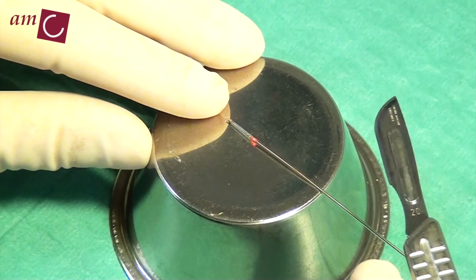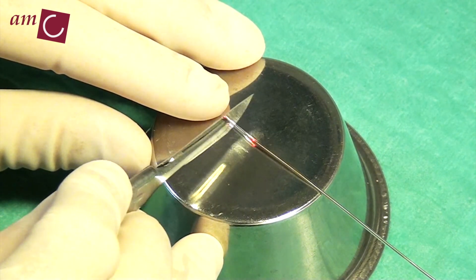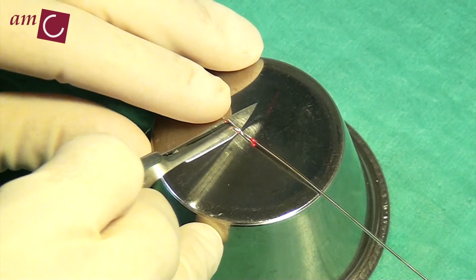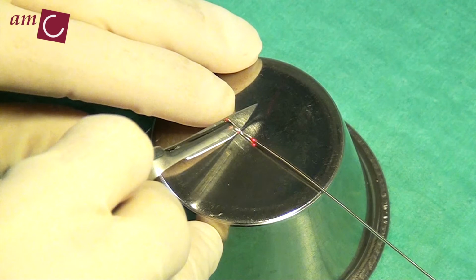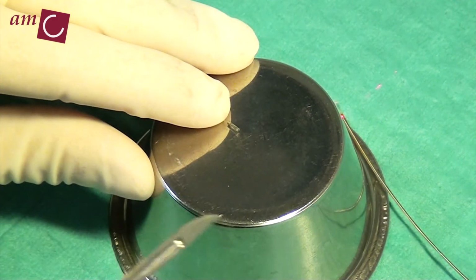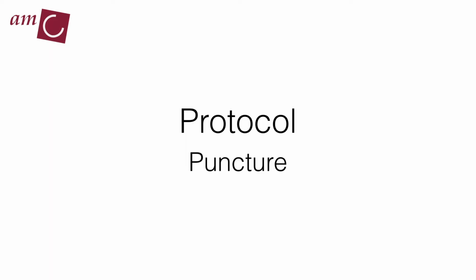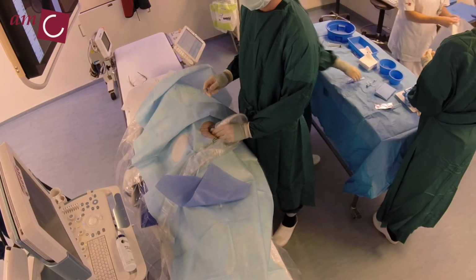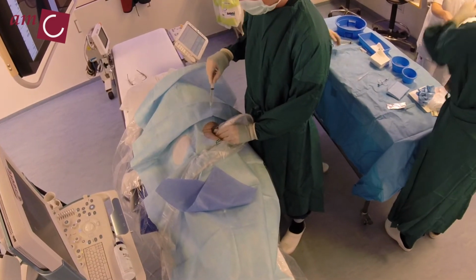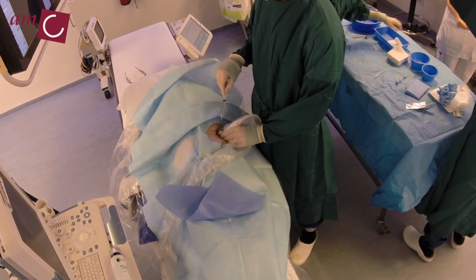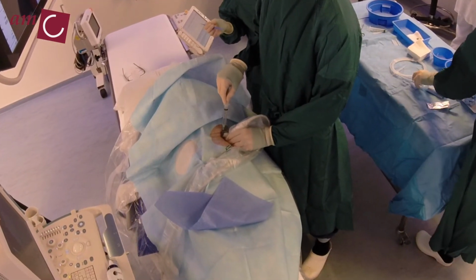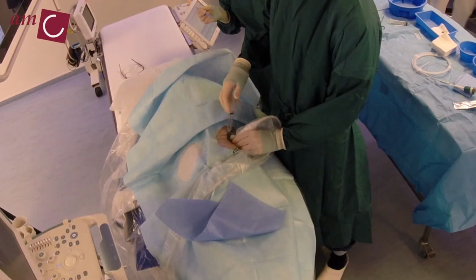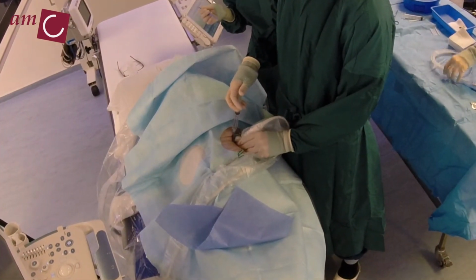Place the probe on a hard surface and use a scalpel to shorten the tip. Cut 5 millimeters distal from the prism using the emitted light for orientation. Fix the distal part of the probe during cutting in order to minimize pressure on the fiber and prism. Anesthetize the skin and deep layers using lidocaine 2%. Wait several minutes, allowing for the lidocaine to take effect. Instruct the patient to inform you in case of pain.